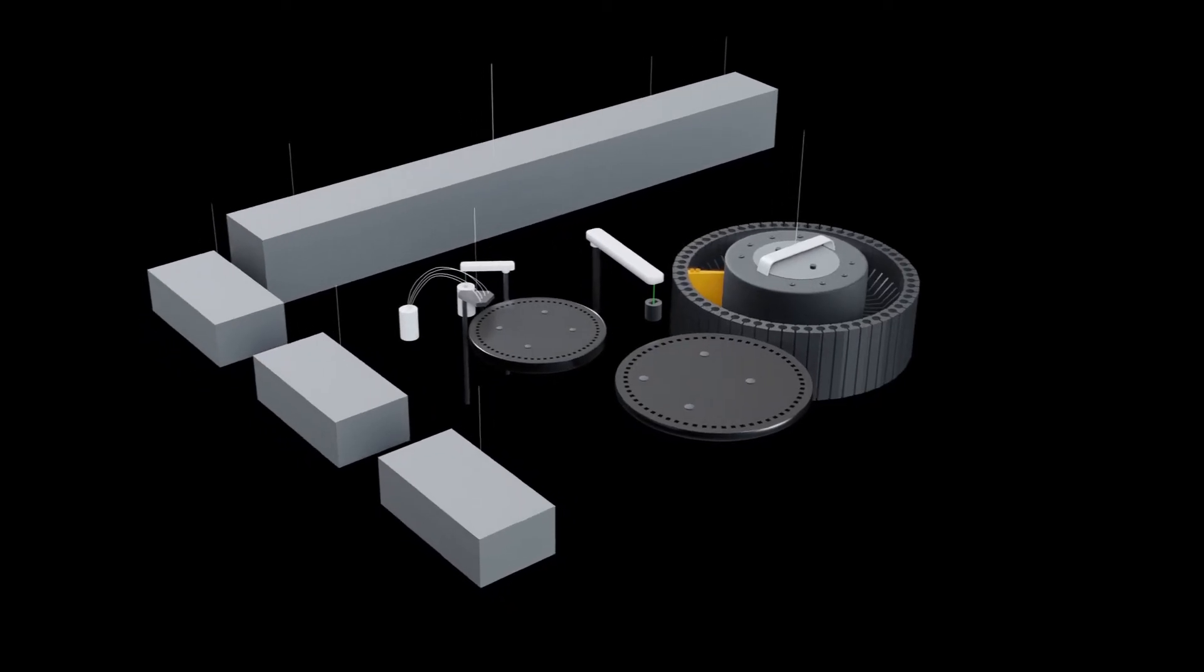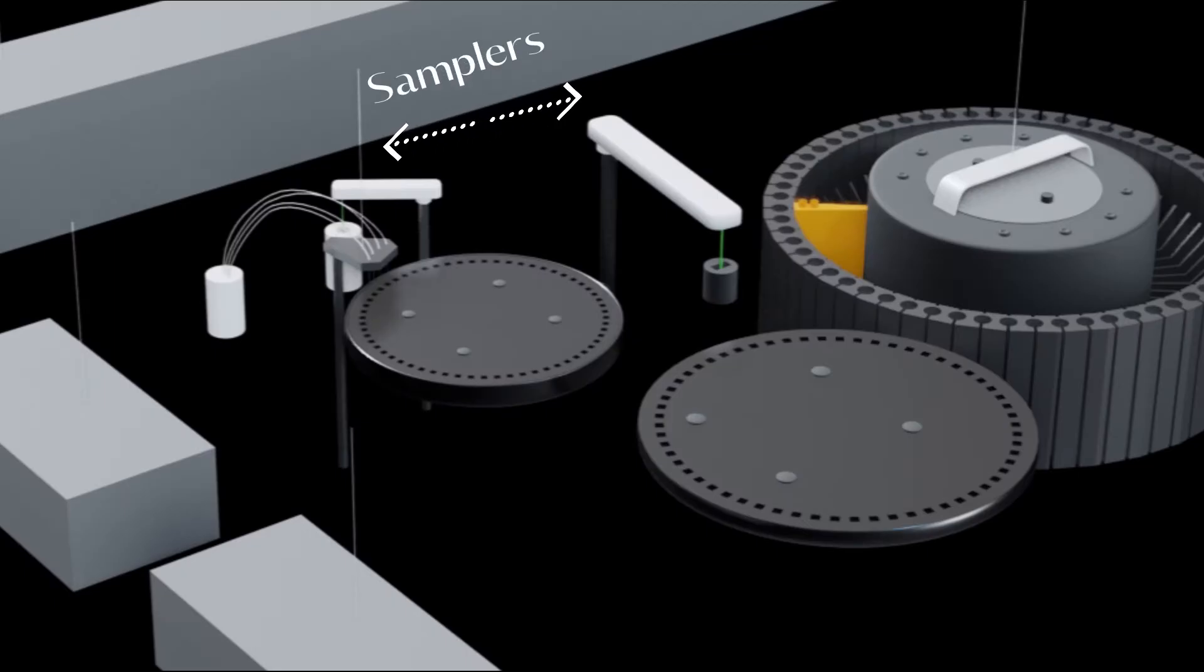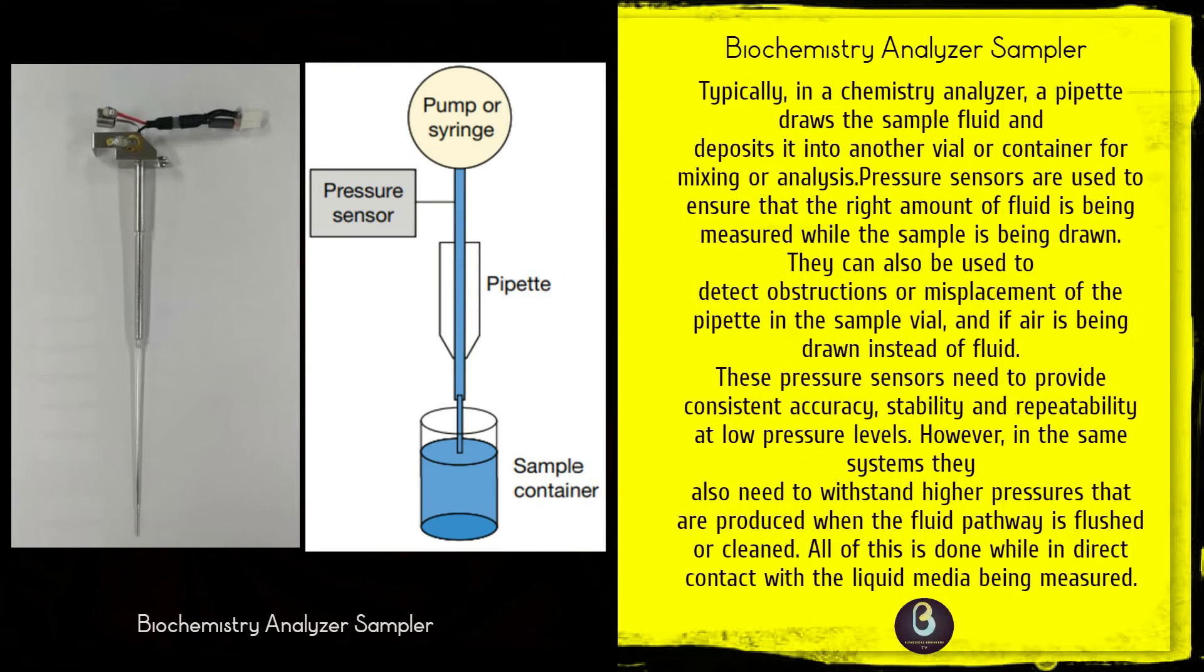Let's look into the sampler first. This module holds the batch of samples awaiting analysis in separate cups on a circular tray which is rotated at intervals. A probe connected by plastic tubing to the proportionating pump enters each sample serially.